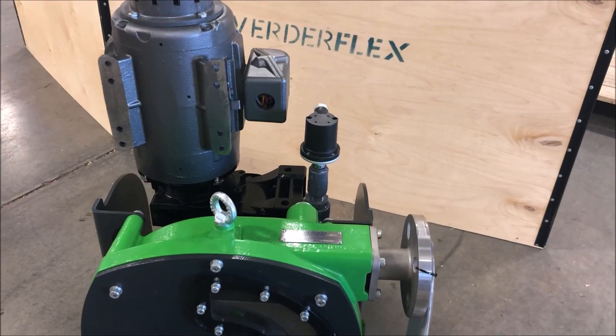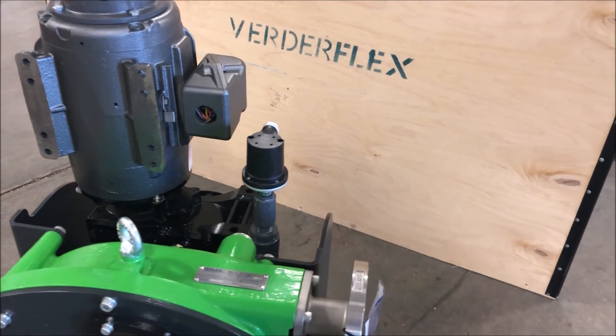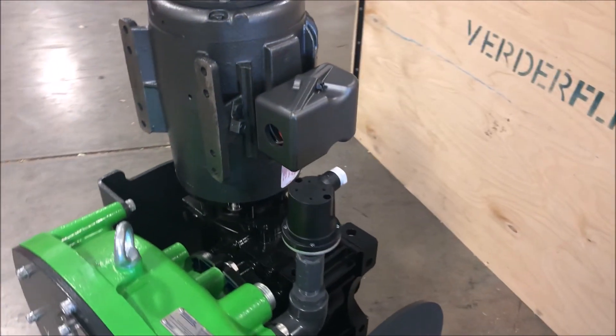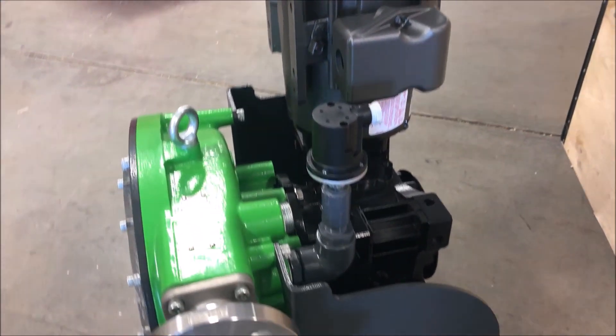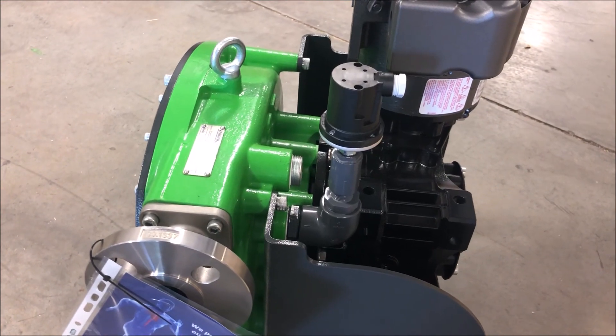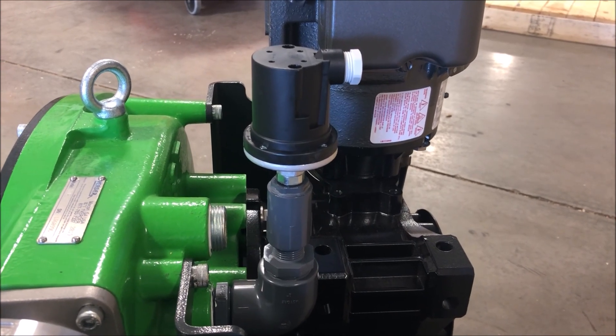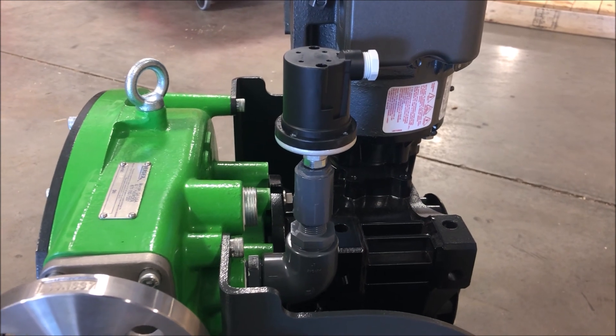The Verderflex hose failure detection system consists of a pressure switch mounted to the fill port at the back of the pump. This pressure switch is non-wetted and trips on the first sign of increasing pressure in the pump casing, which is indicative that the hose is leaking. This switch closes or opens a contact that indicates to the VFD or other control system that the pump needs maintenance and should be shut down.